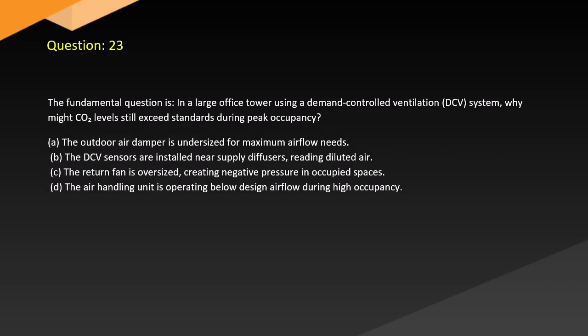Question 23. In a large office tower using a demand-controlled ventilation (DCV) system, why might CO2 levels still exceed standards during peak occupancy? A. The outdoor air damper is undersized for maximum airflow needs. B. The DCV sensors are installed near supply diffusers, reading diluted air. C. The return fan is oversized, creating negative pressure in occupied spaces. D. The air handling unit is operating below design airflow during high occupancy.